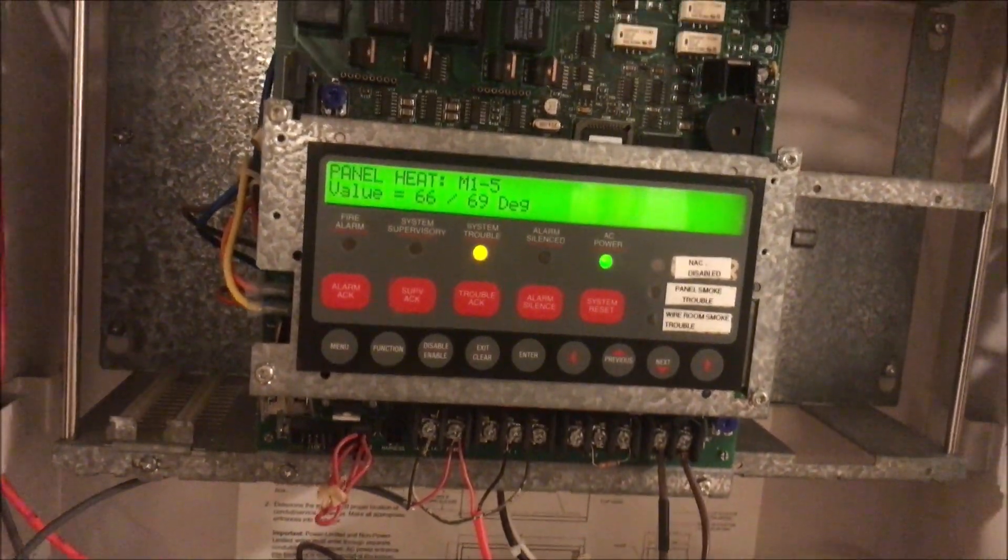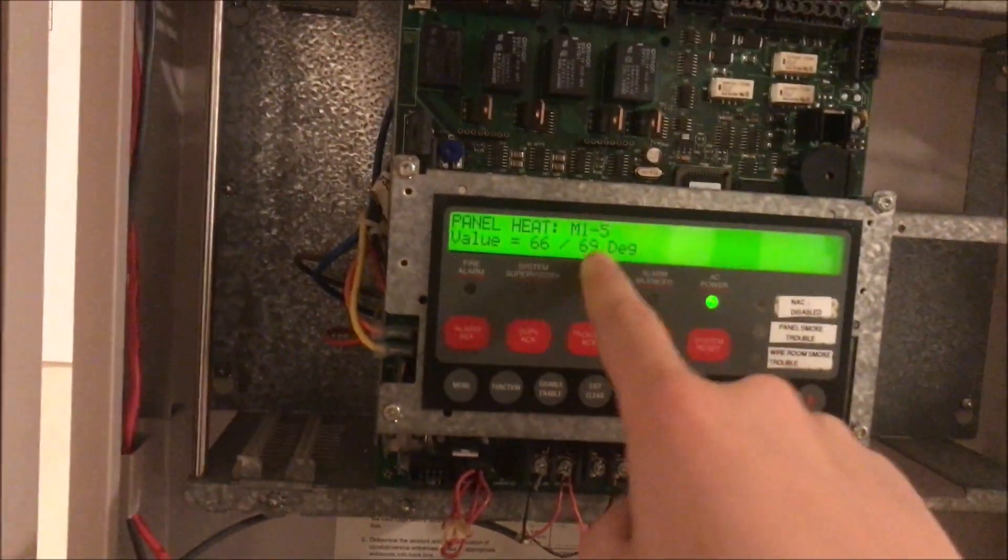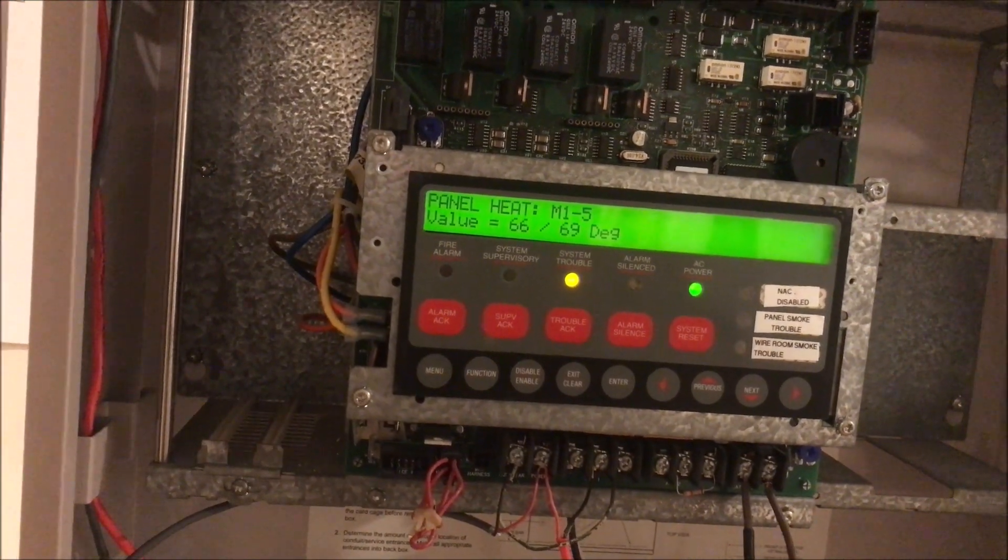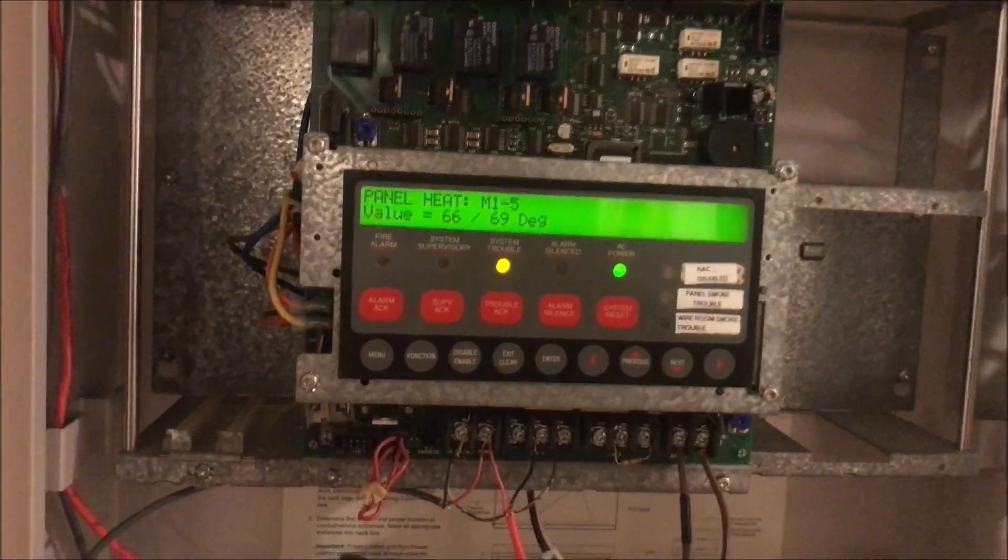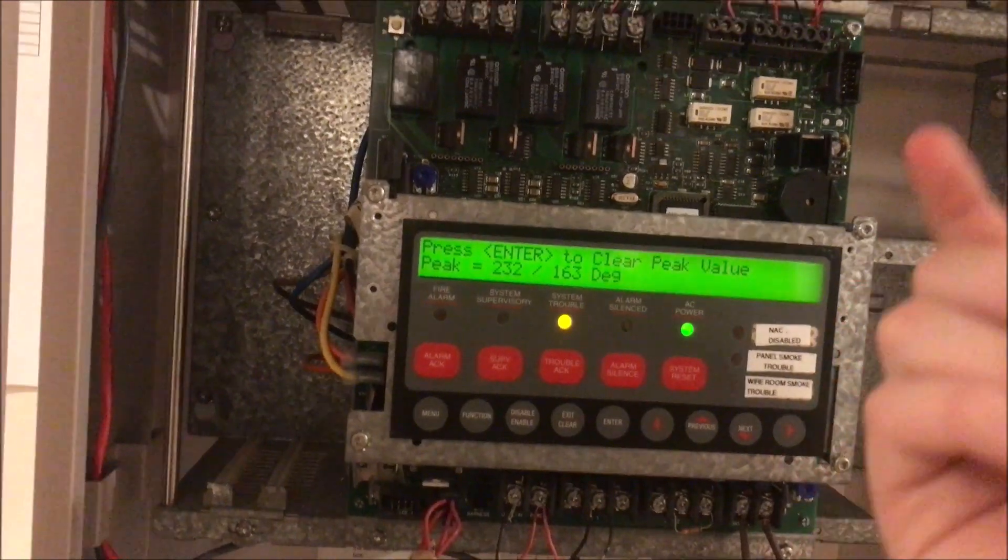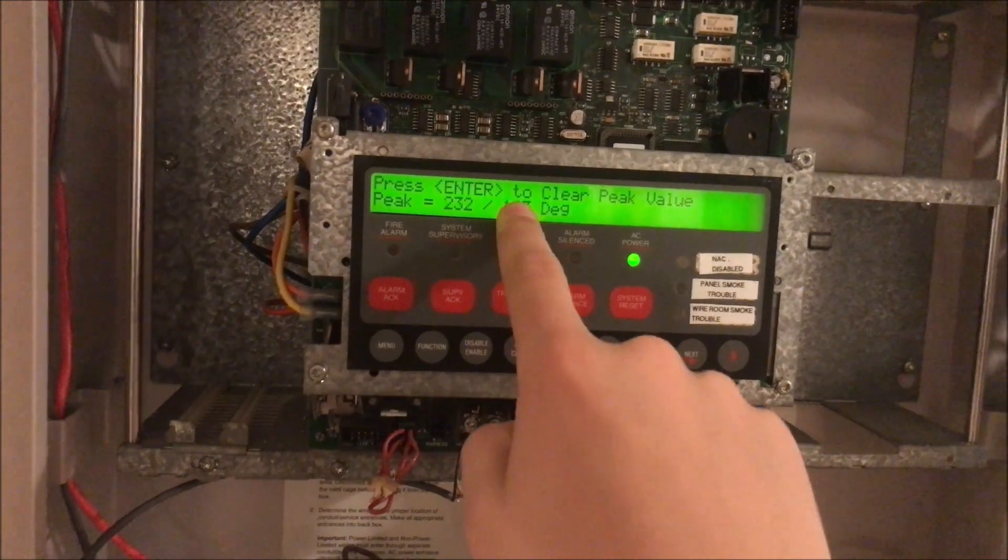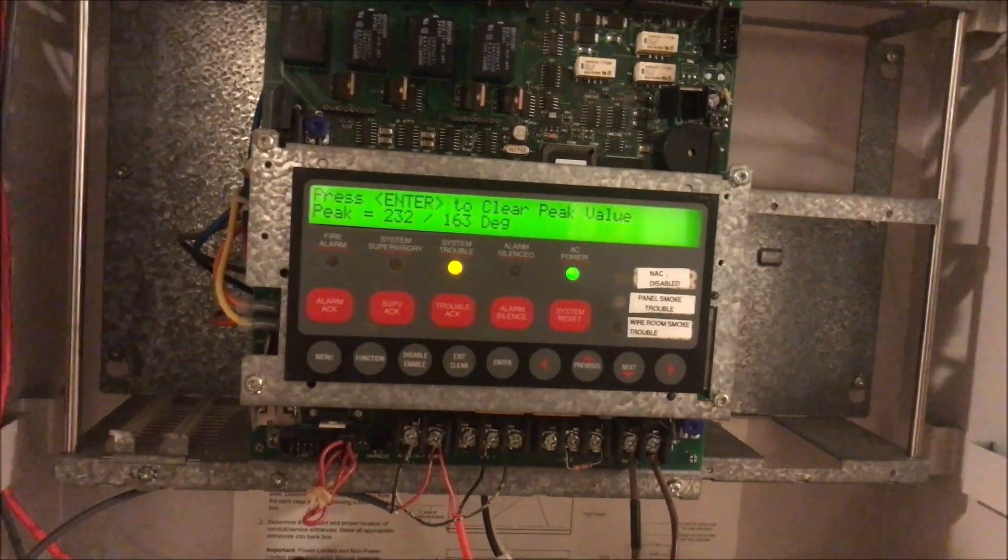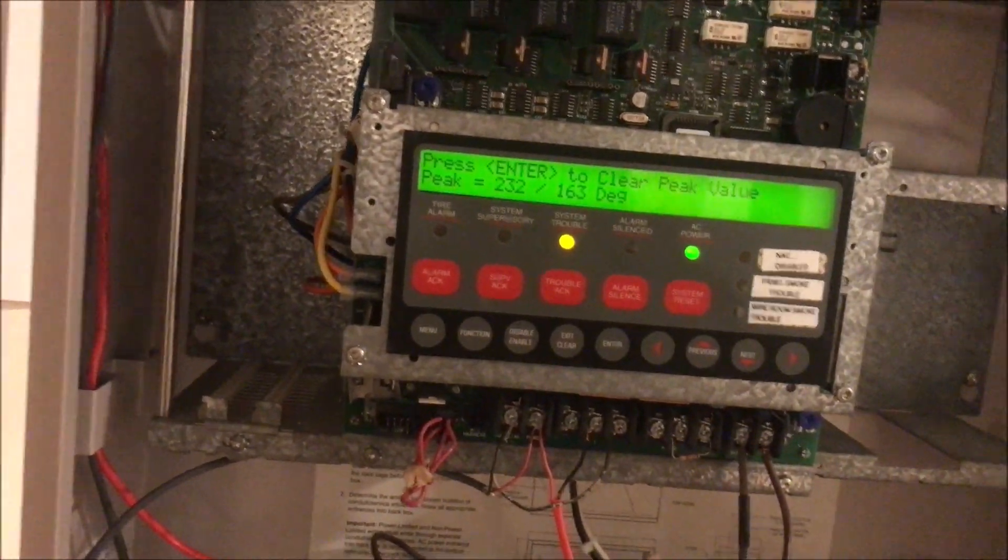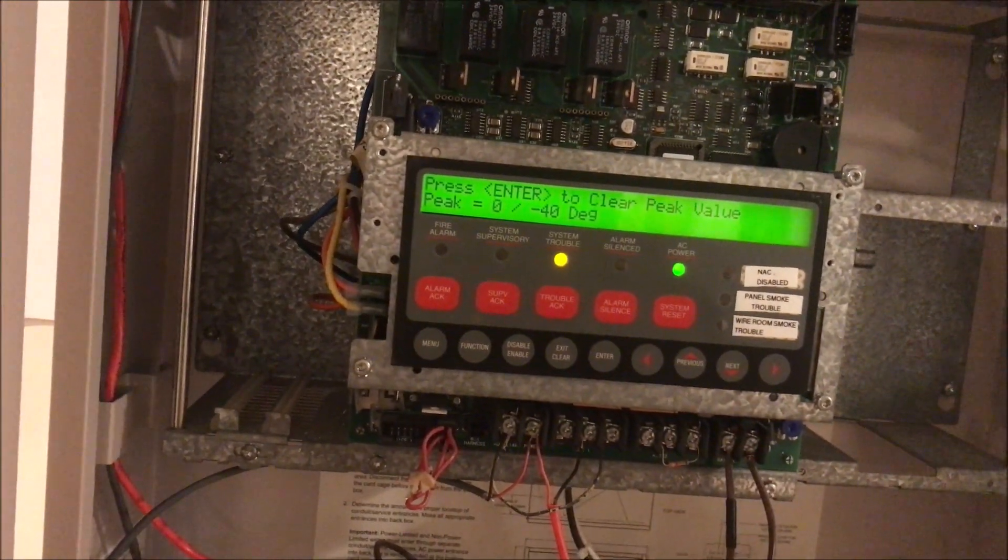Right now the heat detector is sitting at 69 degrees Fahrenheit, and we're just going to ignore that first value. That is the actual ambient temperature of the detector. If you keep going, you can see if the detector trips, it will keep its peak value. The highest it got last time since I had cleared the peak value was 163 degrees, so you can actually go in and see the exact temperature that the detector got.